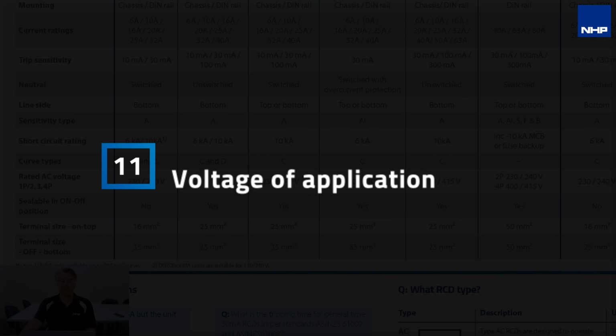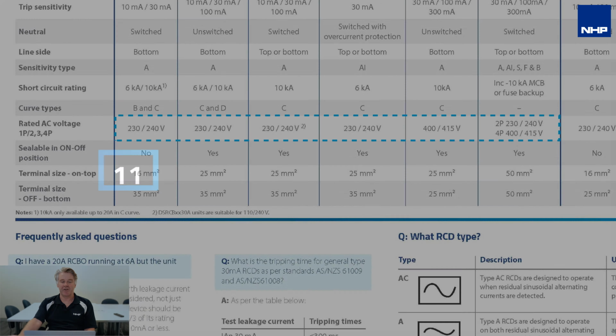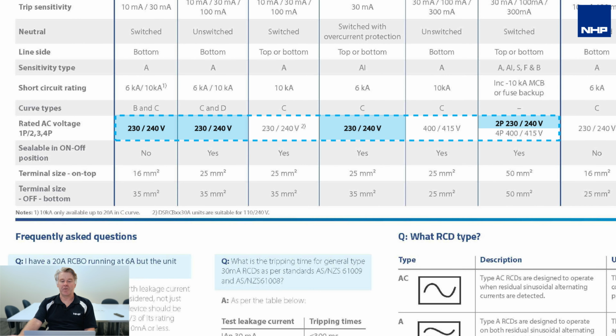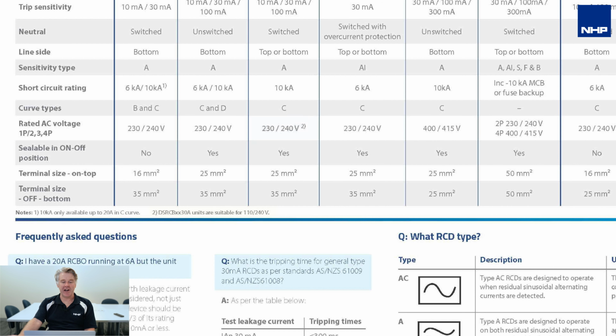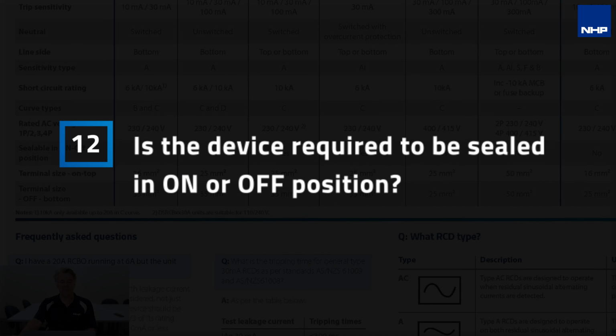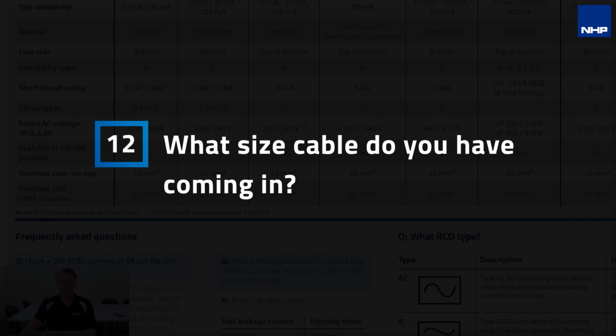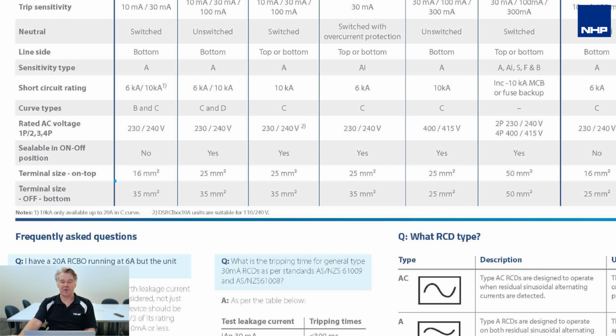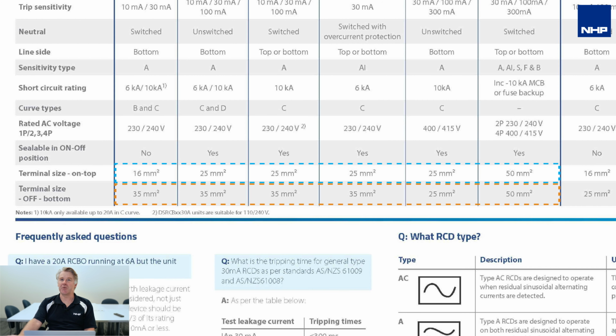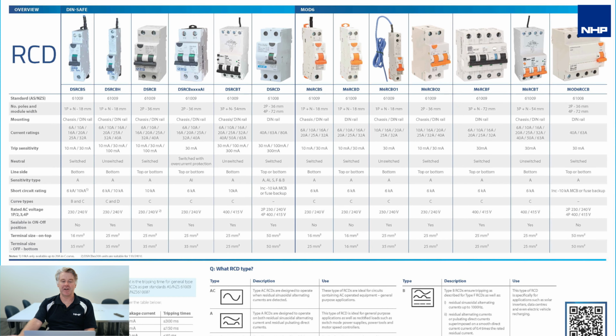Then the voltage of the application, generally speaking, the majority of devices are 230, 240 volt, or for three-phase 400, 415. There are some applications where we can have a 110 volt rating, such as you can see here on the 2-pole wide RCBO. Is the device required to be sealed in the on or off position? What size cables have you got coming in? Will your cables fit? So here's the general for the cables going directly into the terminal. Of course, we do have pin terminals to allow cable reduction. So you may have a 50mm cable and it will reduce it to a 25, so you can fit it in, say, this RCBH column here.